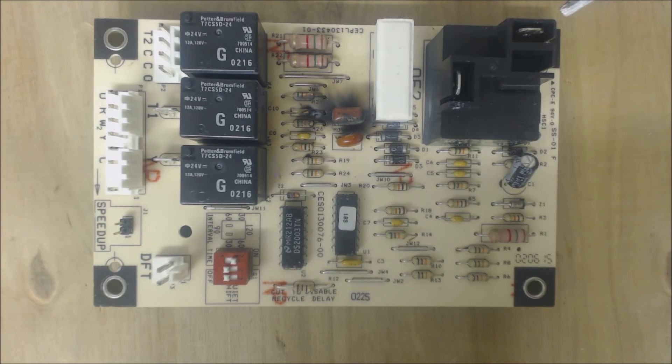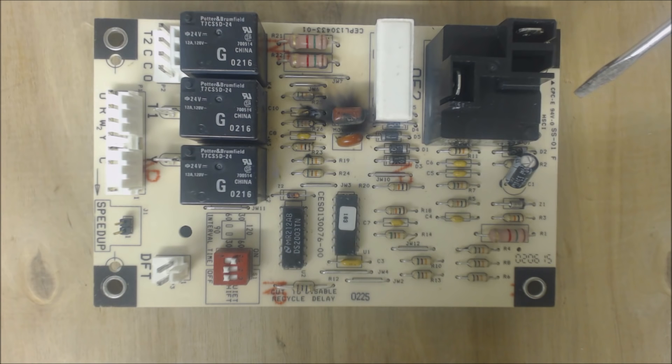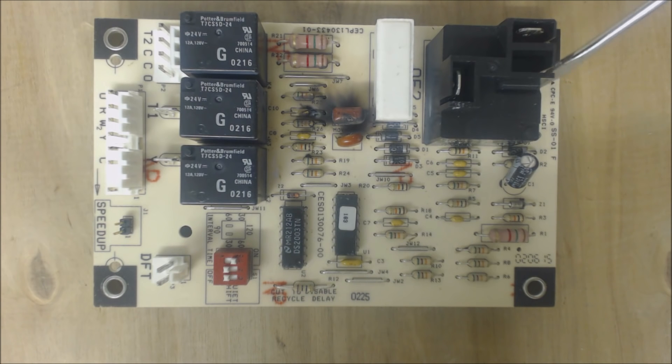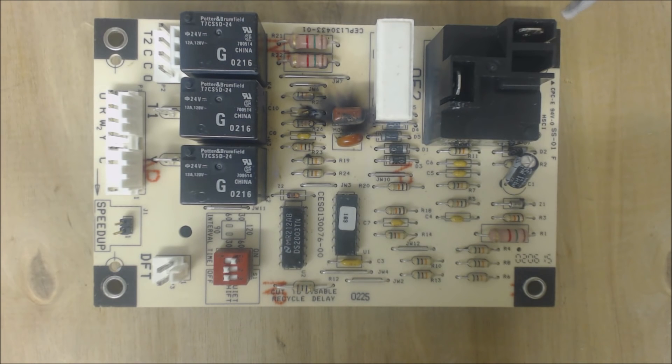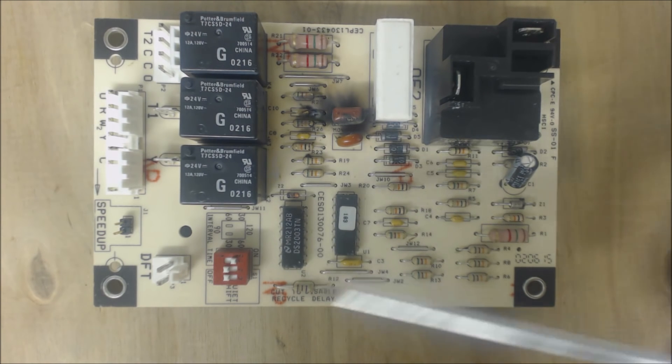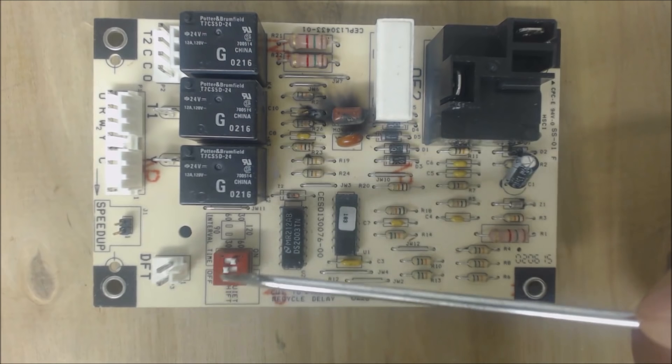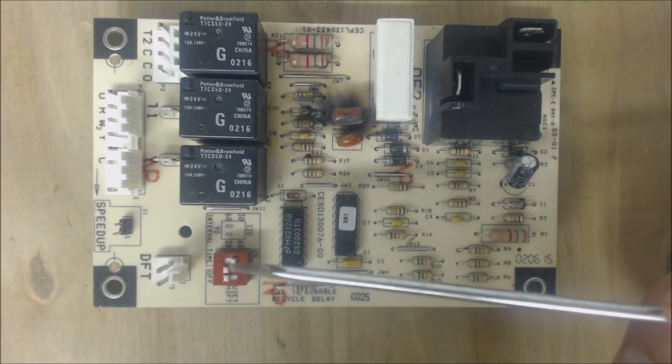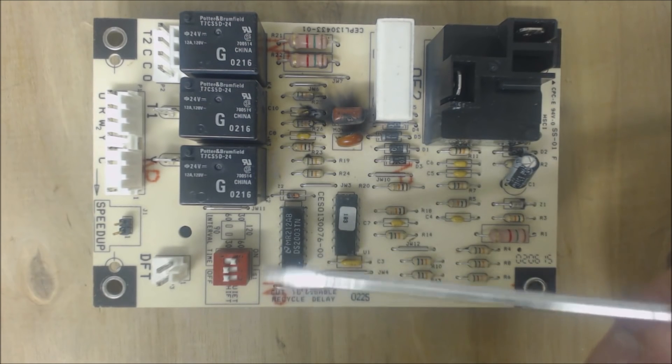You have power coming from the contactor, going through a vapor pressure switch, and coming back to OF1. That is normally closed, and that pressure switch is closed in air conditioning and in heat mode, as well as in defrost mode. Now down here, what we have is our defrost settings.